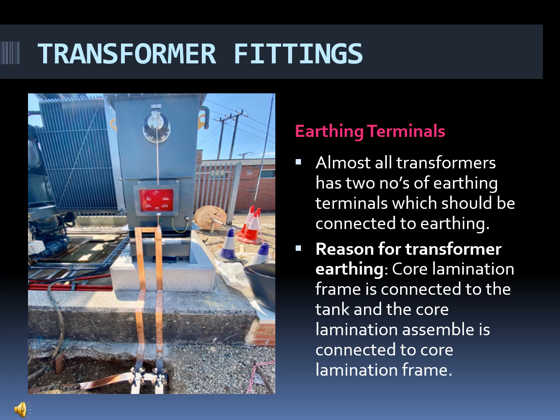The third fitting of the transformer is the earthing terminals. Most transformers have 2 earthing terminals which should be connected to the earthing. Let's understand the reason for transformer earthing. Every transformer, either small or big, consists of a lamination core assembly. The lamination core assembly is connected to the core lamination frame. The core lamination frame is connected to the tank.